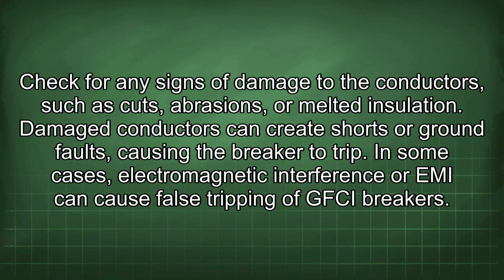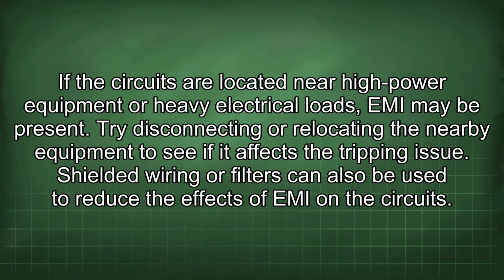Check for any signs of damage to the conductors, such as cuts, abrasions, or melted insulation. Damaged conductors can create shorts or ground faults, causing the breaker to trip. In some cases, electromagnetic interference, or EMI, can cause false tripping of GFCI breakers. If the circuits are located near high-power equipment or heavy electrical loads, EMI may be present.